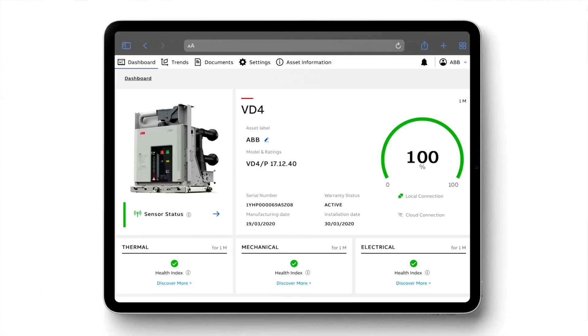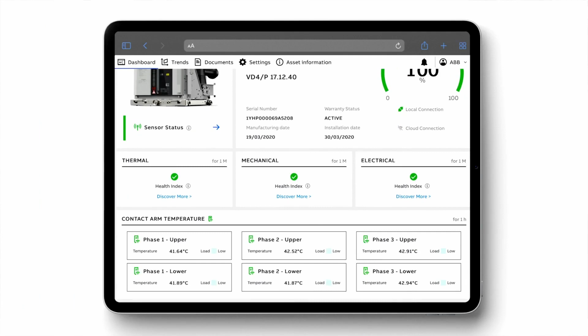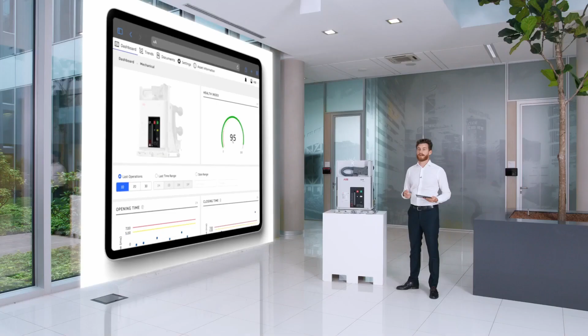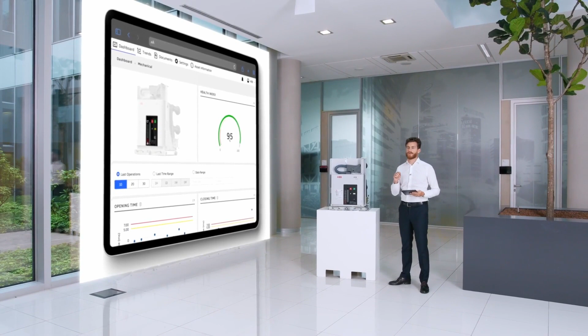Now let's take a look at mechanical actuators check and accessories check. Another typical scenario is assessing the quality of the kinematic chain after years of circuit breaker operation. A maintenance technician will have to shut down the switchgear and withdraw the breaker, following all the safety procedures and using expensive tools, then compare them with the recommended factory settings.